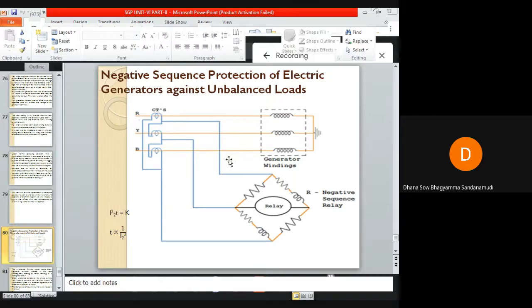Under unbalanced conditions of the three-phase stator winding, the phase currents have negative sequence components. The phase currents of the stator windings of the alternator or generator will have negative sequence components rotating at synchronous speed in a direction opposite to the direction of rotation of the rotor. Therefore, double frequency currents are induced in the rotor.